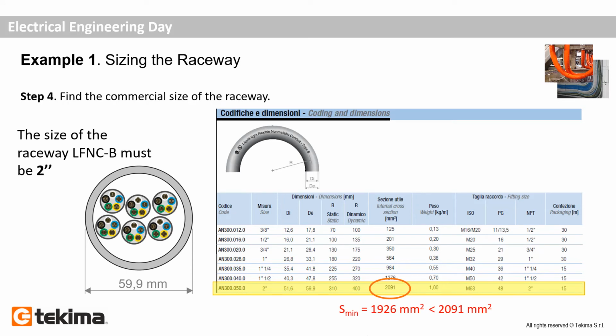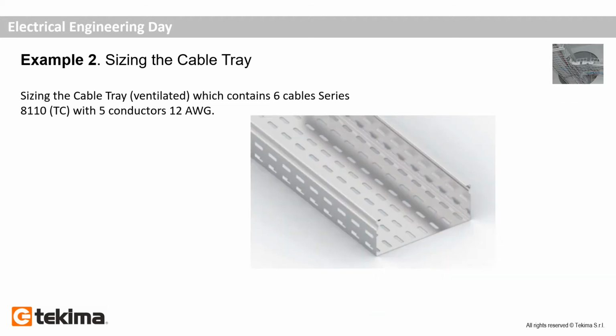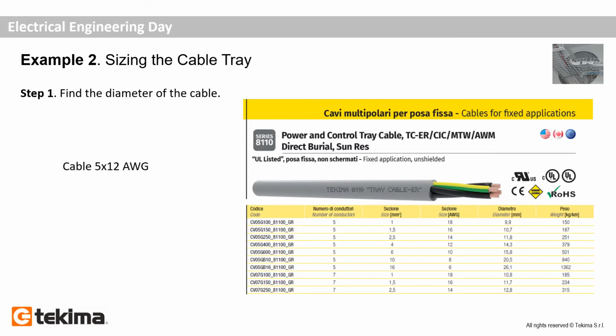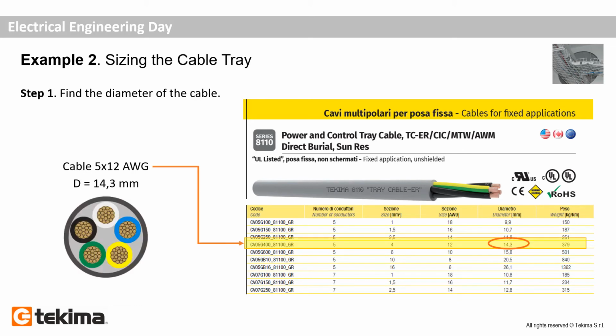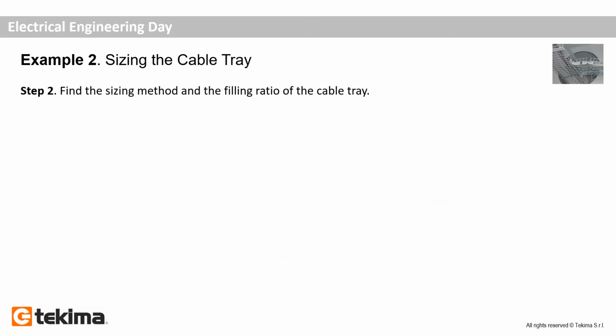That means a raceway with an external diameter of approximately 59.9 millimeter. As a second example, we will size the cable tray which contains the same cables that we have seen installed in the raceway in the example before. And let's consider a ventilated cable tray. As a first step, we have to find the external diameter as in the example before, which is again 14.3 millimeter. As a second step, we have to find the sizing method of the cable tray.